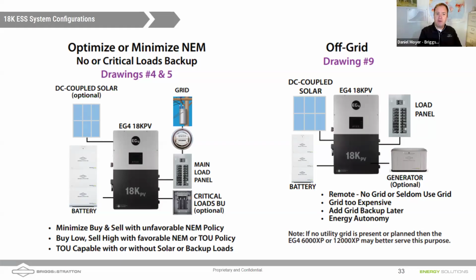Also, there is the battery and the DC coupled solar. Now, like EG4 said, the critical loads backed up panel is optional. You could install a battery with one of these inverter systems and not back up anything. You could be using it to do time of use arbitrage. The DC coupled solar is optional. You could absolutely have a backed up loads panel and still do battery backup without solar. And that's becoming more and more common.